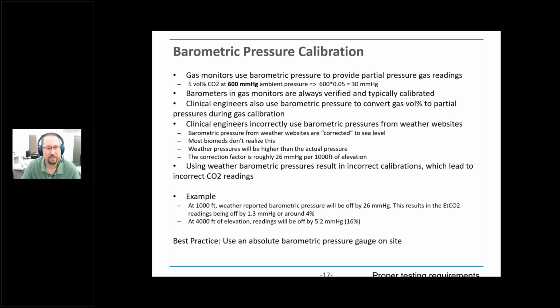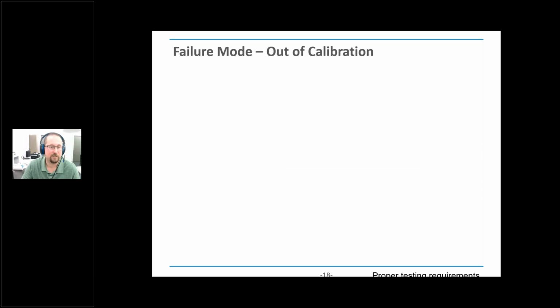And so this feeds into the last one I want to talk about, which is the failure mode of just being out of calibration. So this is talking about the actual sensor within the device. We saw and have heard stories and interviewed people where they just used their own gas to do the calibration. It happens. They might be testing device A over here and they go over to test device B and just use the same gas for both, but most of the time the OEMs will call out a very specific gas you're supposed to use.